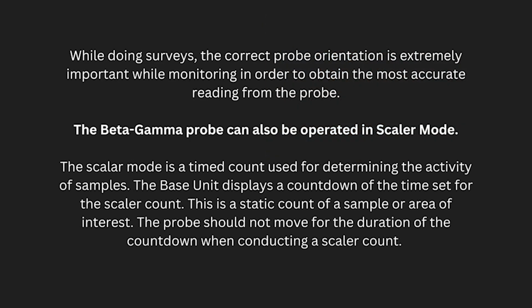While doing surveys, the correct probe orientation is extremely important while monitoring in order to obtain the most accurate reading from the probe. The beta-gamma probe can also be operated in scalar mode. The scalar mode is a timed count used for determining the activity of samples. The base unit displays a countdown of the time set for the scalar duration. This is a static count of the sample or area of interest. The probe should not move for the duration of the countdown when conducting a scalar count.